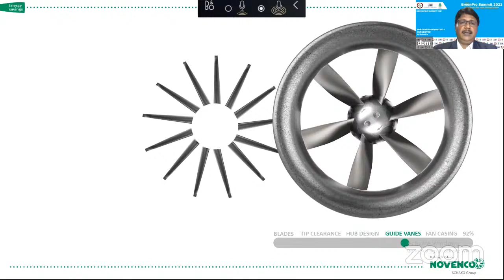And now there are guide vanes. We have given the guide vanes because any air moving through any fans has a tendency of rotation, and after rotation the air becomes very turbulent. So to minimize that turbulence, we are providing the guide vanes, and because of that uniform distribution of air is taking place.